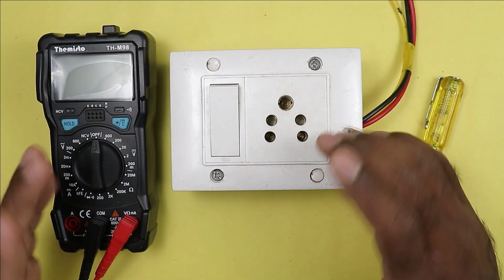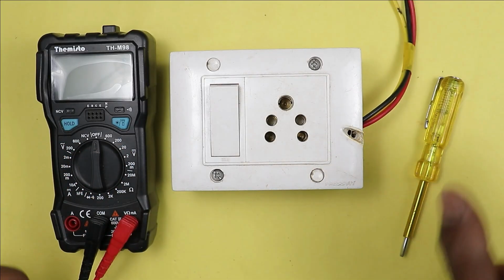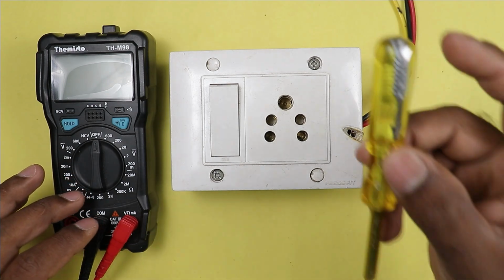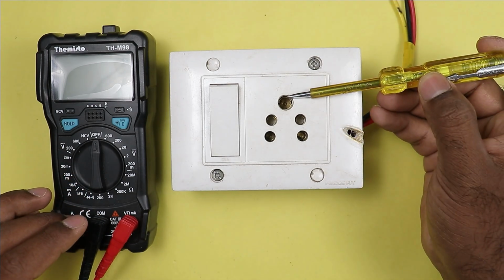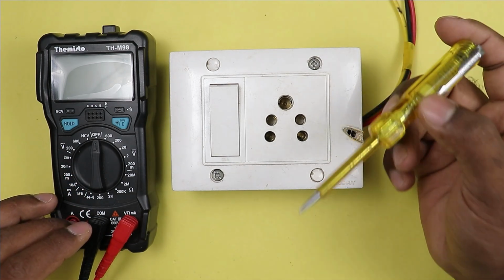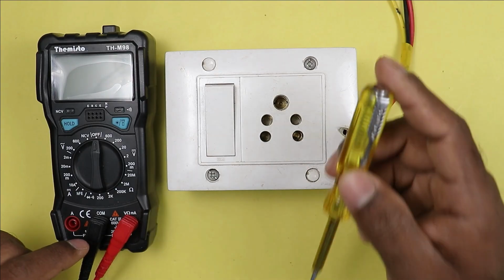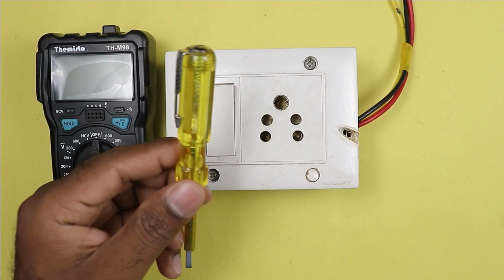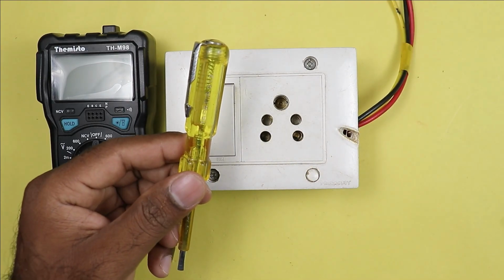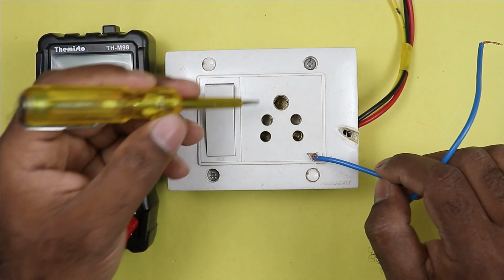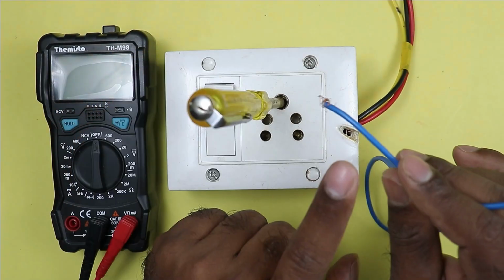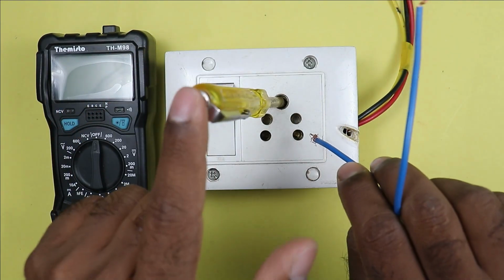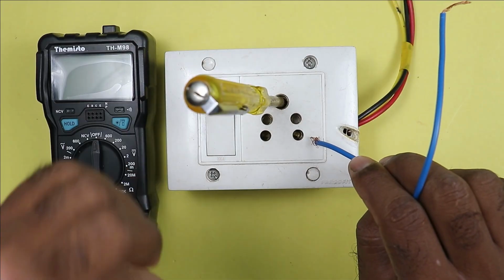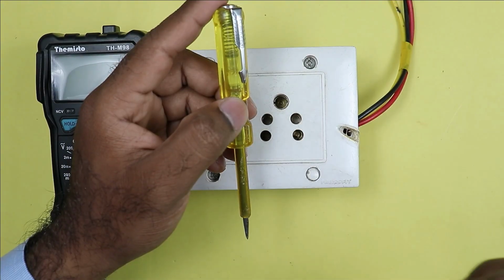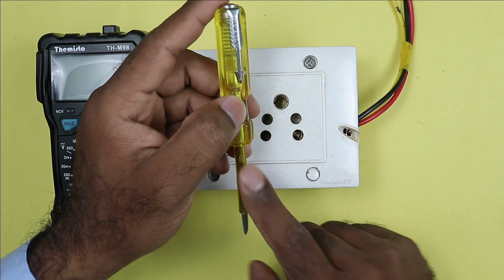Friends, do not trust the tricks of these electrical scientists on YouTube. They say you can check the earthing through your tester, but that is a completely wrong way to check. The problem with checking earthing through a tester is that first of all, you have a high chance of getting an electric shock, because if you connect this wire to the phase supply and connect it here, and accidentally touch it, you will get an electric shock. The second thing is that you can never properly check the earthing through a tester.